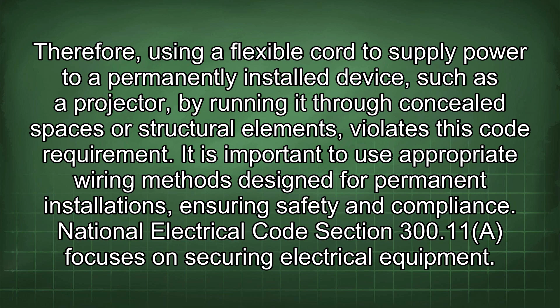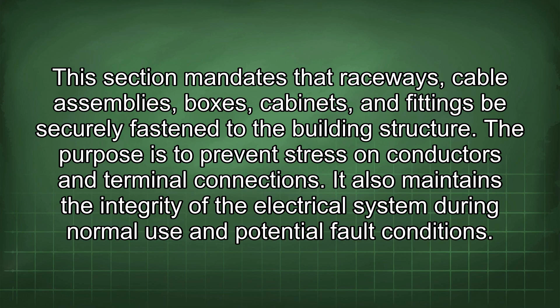National Electrical Code Section 300.11 focuses on securing electrical equipment. This section mandates that raceways, cable assemblies, boxes, cabinets, and fittings be securely fastened to the building structure. The purpose is to prevent stress on conductors and terminal connections. It also maintains the integrity of the electrical system during normal use and potential fault conditions.